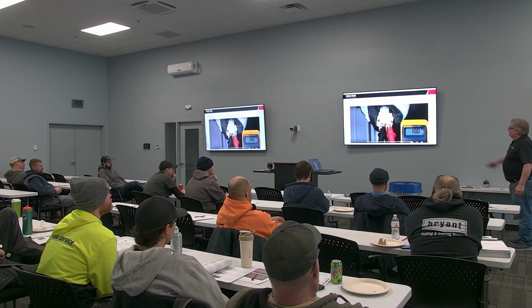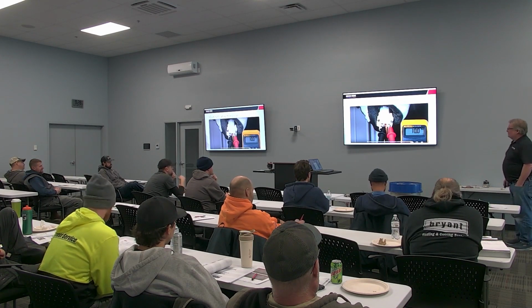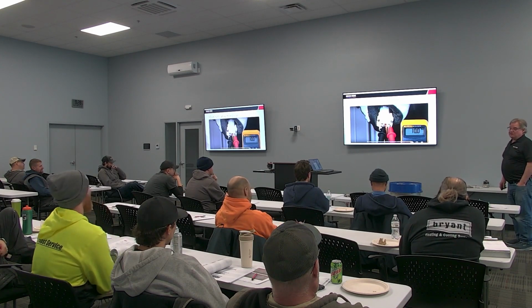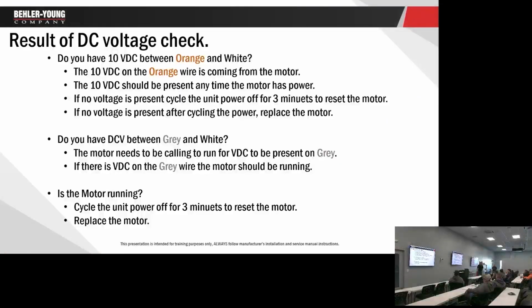Okay. So again, check it for DC. Should be 10 volts DC on orange all the time. So do you have 10 volts DC on orange? If the motor's powered up, I should. If not, reset power before faulting the motor. Otherwise, the motor's bad. Energize a call for blower, R to G.